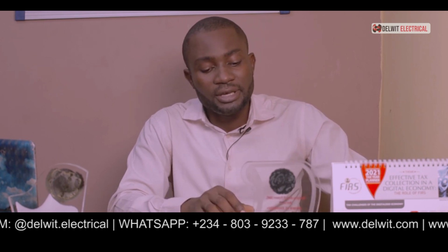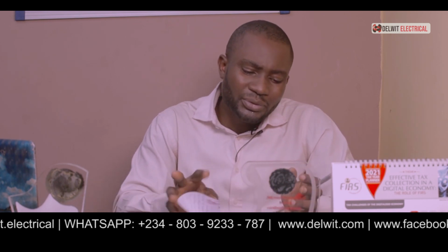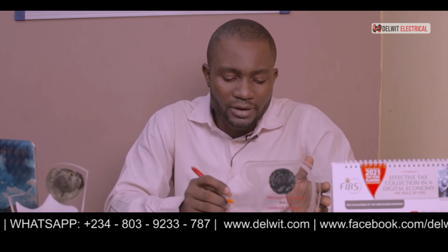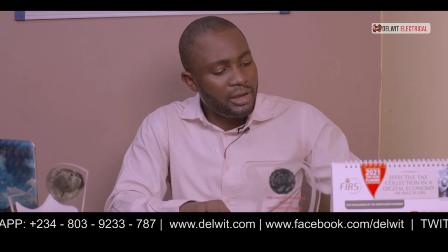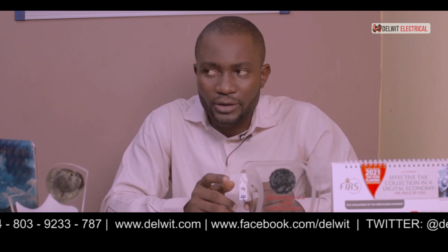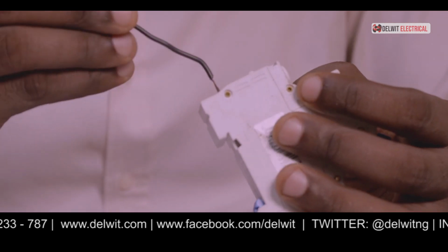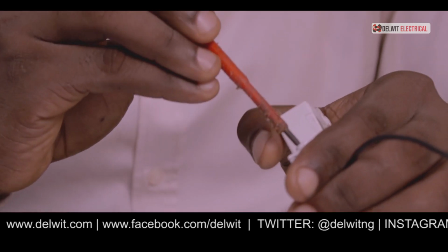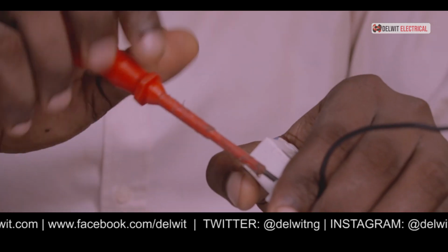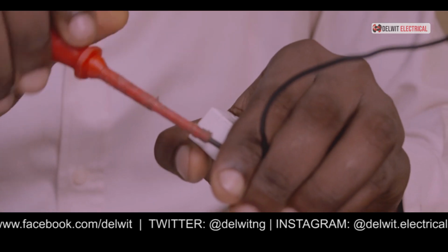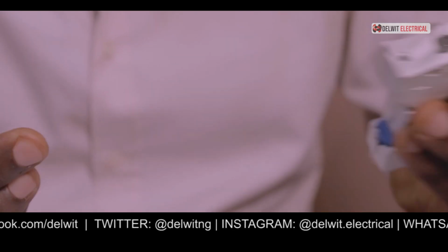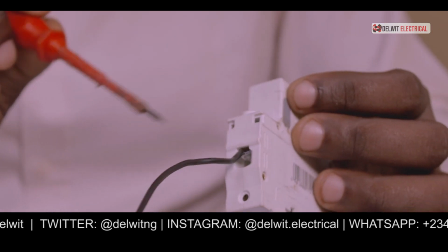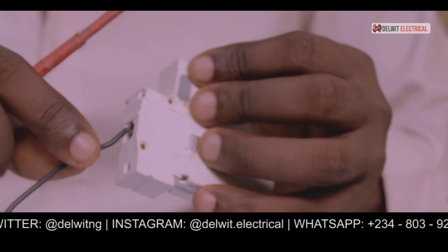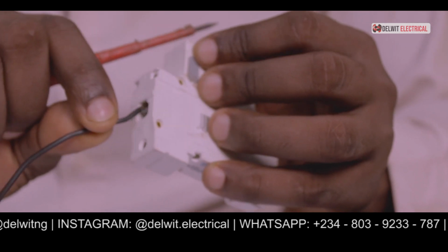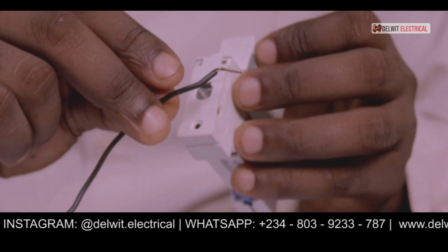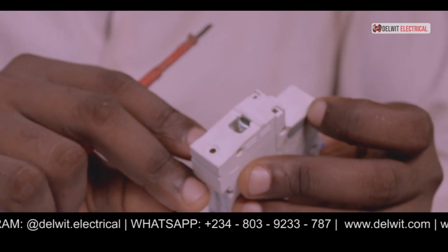So these are the three basic faults that can trip, but there are other little faults that can happen along the line. For example, loose or corroded connection. Now, if you look at this circuit breaker, you will see that it's meant to be connected here. But because of the hurriedness of some people, they might not clip it appropriately. So it will be loose. And when it's loose, it has every tendency to fall off. And when it falls off, it touches the body of the distribution board, and that will lead to a fault.